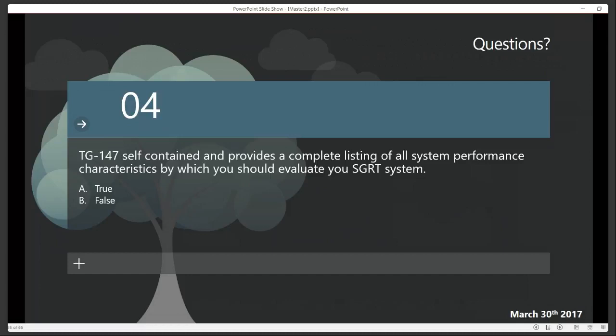What is your QA tolerance? My QA tolerance, for my monthly verification of the SGRT system, I do a hidden target test end-to-end, ISOCAL, and all of that has to be around or below 0.3 of a millimeter, including imaging. I do a Winston Lutz test with just the SGRT system setup and then an SGRT and imaging setup. The SGRT and imaging setup is the end-to-end performance spec that we use because that's what we do for SRS. That is the one that's 0.3 of a millimeter or less.